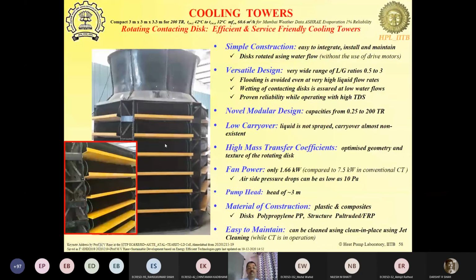There is the cooling tower, a 200-ton cooling tower which we had built, integrated, and deployed. Okay. And the conventional cooling tower had a power consumption of 7.5 kilowatt for the fan. Ours, at that time, the first unit, was 1.66. Now we have reduced this down to 1.5 kilowatt. Okay. This is mainly because of the low pressure drop across this. So all 6 sides of the hexagon are active mass transfer units in this case.